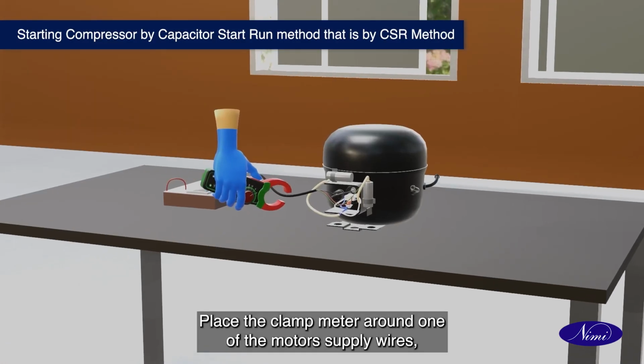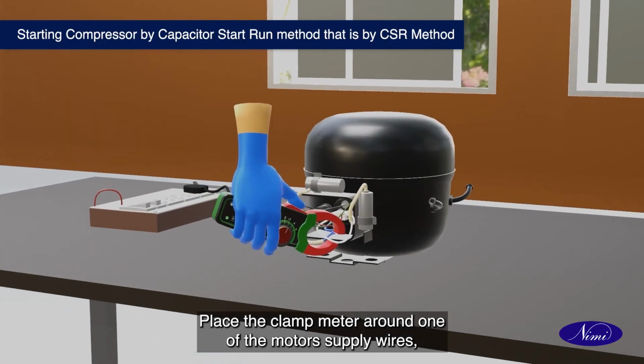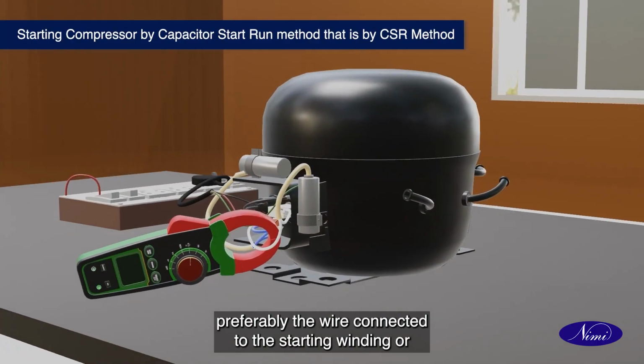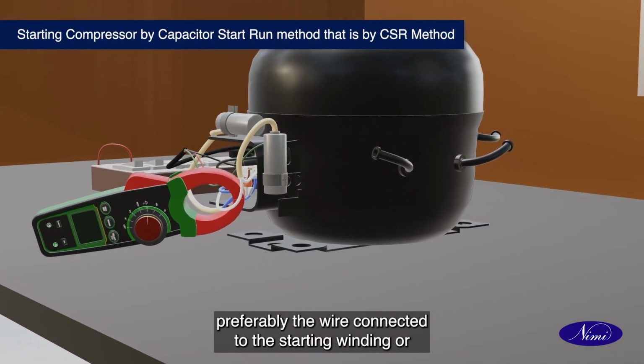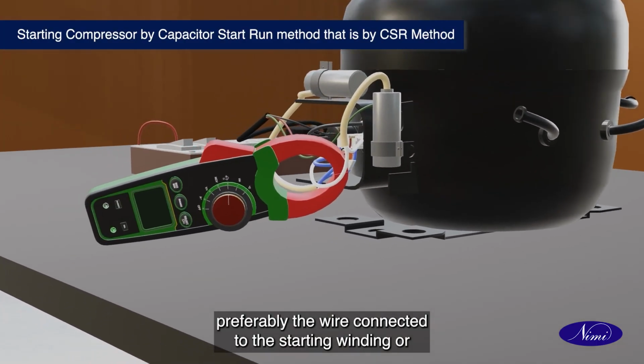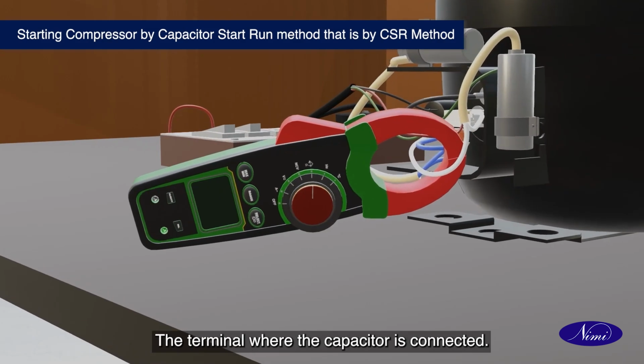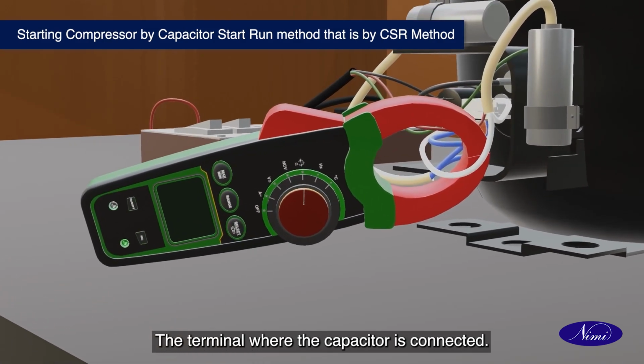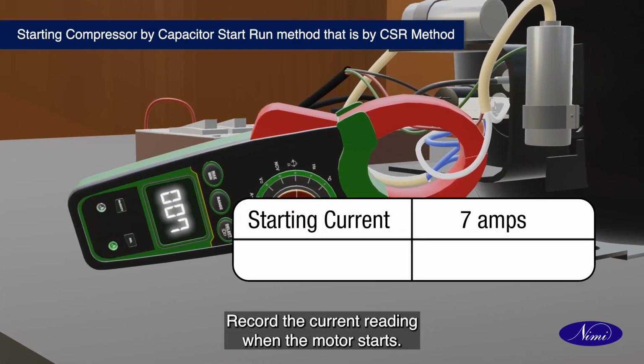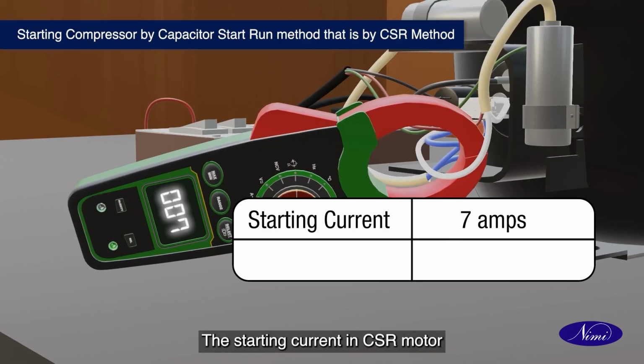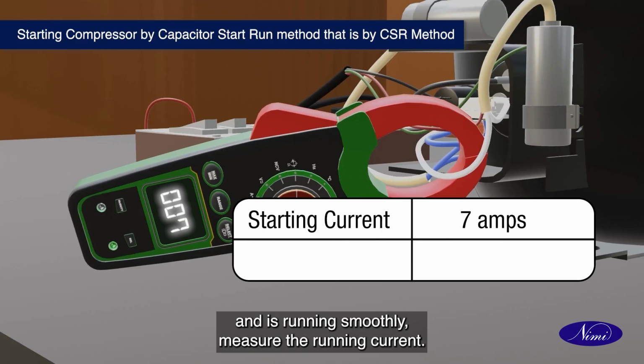Place the clamp meter around one of the motor's supply wires, preferably the wire connected to the starting winding or the terminal where the capacitor is connected. Record the current reading when the motor starts. The starting current in CSR motor tends to be higher than the running current. After the motor has stabilized and is running smoothly, measure the running current.